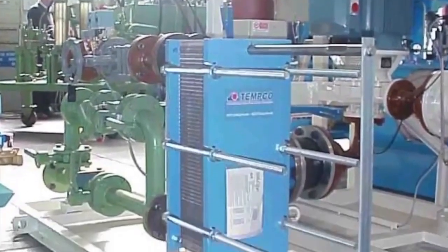And to give a banal example, if we have a pump with a 100 kilowatt engine, the thermal power to be removed from the oil circuit is equivalent to 30-50 kilowatt. Another crucial factor is oil viscosity, but we'll discuss it later.